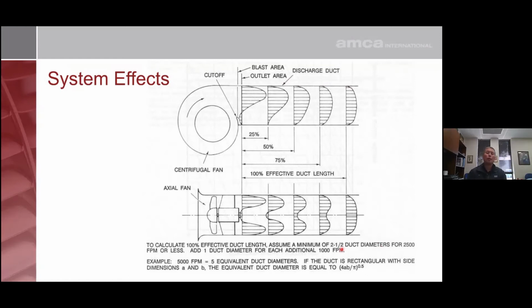for the first 2,500 feet of velocity, you should have 2.5 duct diameters. And for each 1,000 feet of velocity afterwards, you should have another additional duct diameter. So if you have 5,000 feet velocity, you should have 5 duct diameters. If you have 10,000 feet of velocity, you should have 10 duct diameters. If you have 1,500 feet of velocity, you should technically have 2.5 duct diameters. Now, the one thing I just want to mention in the graph is that at 50% here, you probably have about 80% of your regain.